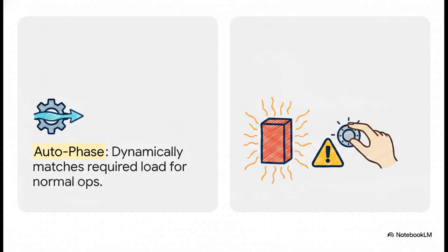So, while autophase dynamically matches the required load for your normal operations, the other modes have very specific, narrow uses. Preset phase acts as a really solid backup if your power measurement circuit fails. It applies a fixed conservative resistance based simply on how many legs are currently active, though it does dissipate more energy than is strictly necessary. And then there's manual phase. You really need to ensure you stay completely out of manual phase, where a user inputs a manual 0 to 100% value. Unless you are specifically commissioning or testing the electrical equipment under very controlled conditions, just stick to autophase.